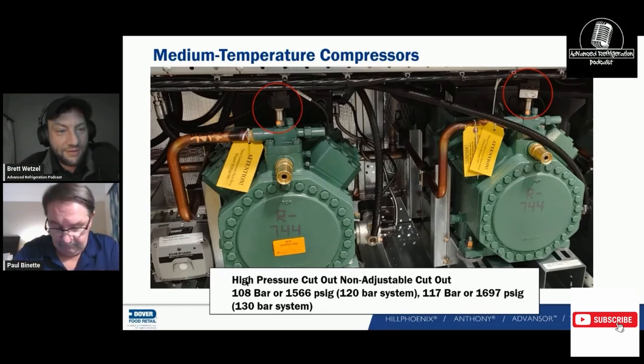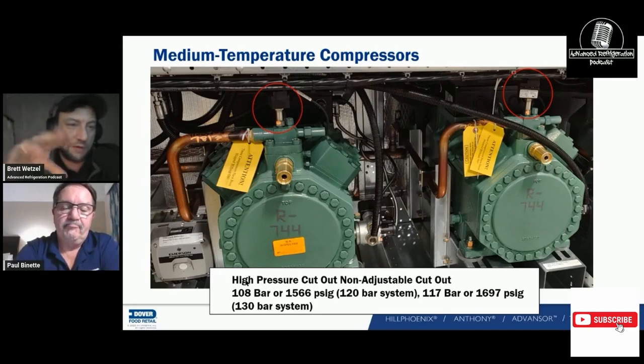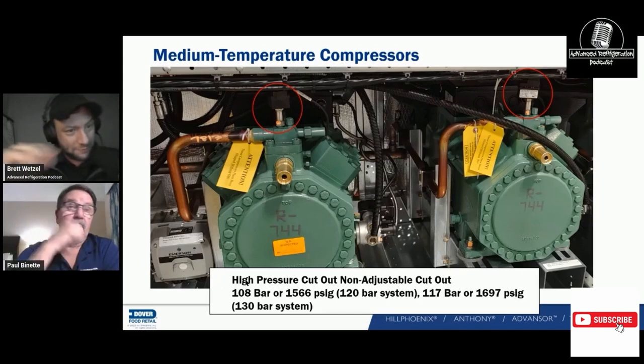We were getting a lot of fills — the sensor was seeing light instead of oil, so it continued to fill. There was a question about HP sensors needing to be at a certain angle — about 5%. Since we're talking about photo-optic sensors, the rack would technically have to be level, otherwise that affects the reading. If a rack is slanted down toward the oil side, and compressors are grenading because the oil is all sitting toward one end, that's going to affect the sensor.